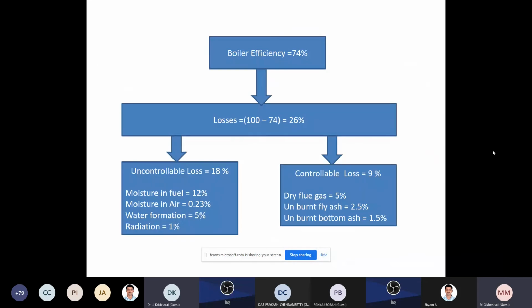Now, also there is a very important thing. See, there are two types of losses. One is called the uncontrollable losses, another is the controllable. Uncontrollable losses means those which we don't have any control over, like moisture in the fuel. You cannot control it, because the fuel is delivered that way, so it will be coming directly. Moisture in the air, depending on the humidity, water formation, and radiation. So these are called the uncontrollable losses.